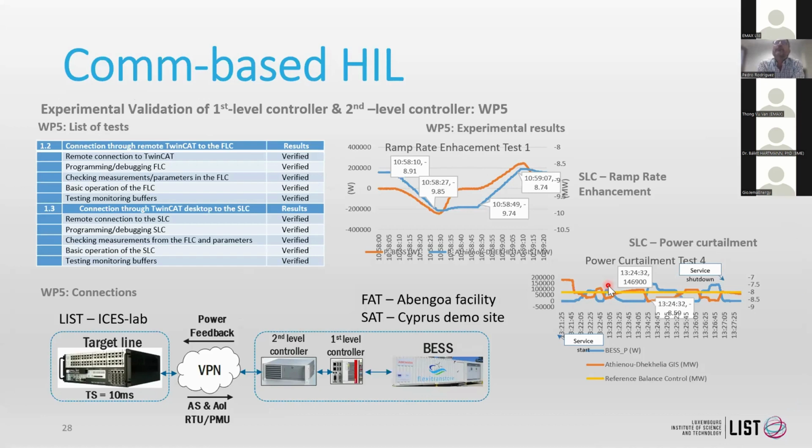In the beginning, during the commissioning stage, the battery and controllers were responding to the signals generated by this virtual environment. In such a way, it was possible to test the response of the battery under many different conditions under control.